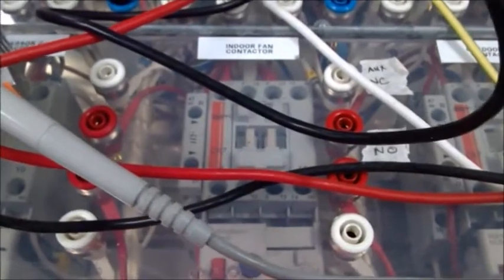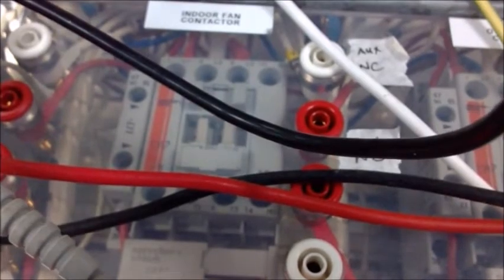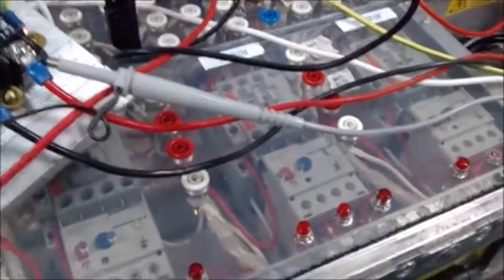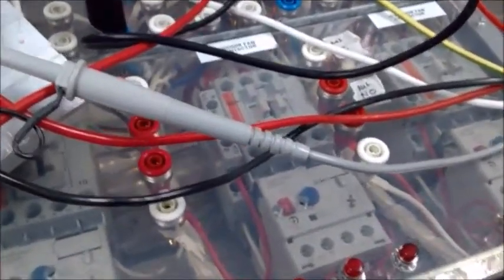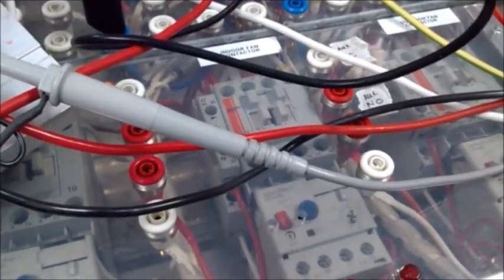You can see for yourself that when we've got 100 percent duty cycle, no problem. But as we start to regulate it... see the little residual feedback there? And then... not good, is it? I better turn that off because they'll probably get mad at me for doing that to the gear. You can see that the mechanical contactor is going to wear out pretty fast if we start giving it that kind of abuse, trying to expect that it's going to switch an output to a heater and have a successful long-term life, which it won't.